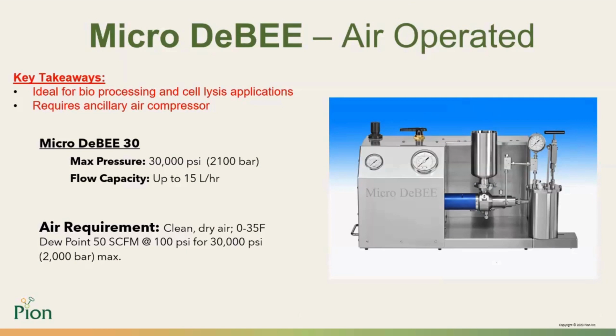Next, we have the Micro DeBEE. The Micro is a benchtop pneumatically driven homogenizer. Key takeaways for the Micro: it's ideal for bioprocessing and cell lysis applications. It does require an ancillary air compressor, the air requirement being 100 psi of clean, dry air. The Micro DeBEE 30 has a maximum pressure of 30,000 psi, a flow capacity up to 15 liters per hour. Just like the Nano DeBEE, the Micro DeBEE is 100% scalable.